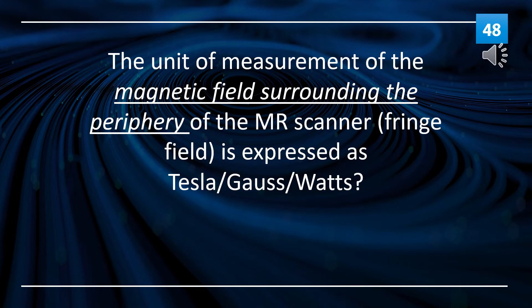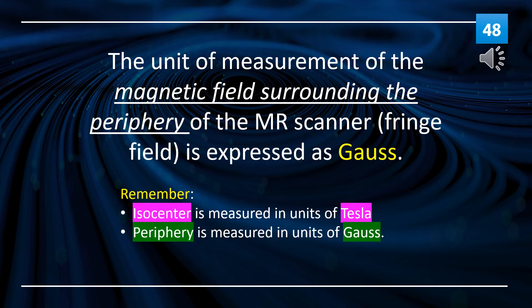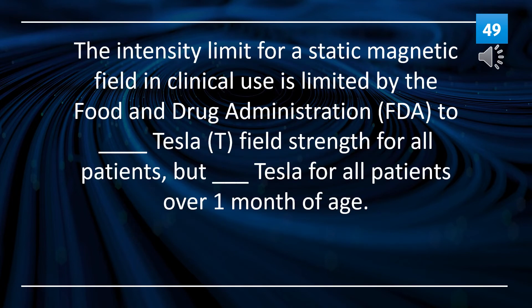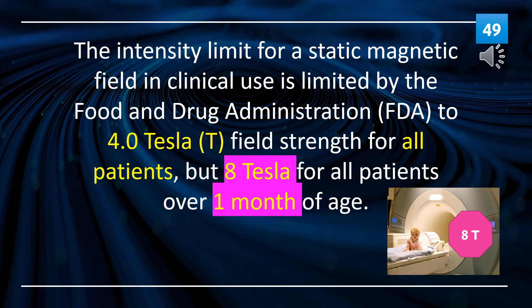The unit of measurement of the magnetic field surrounding the periphery of the MR scanner (fringe field) is expressed as Gauss. The intensity limit for a static magnetic field in clinical use is limited by the FDA to 4 Tesla for all patients, but 8 Tesla for all patients over one month of age.